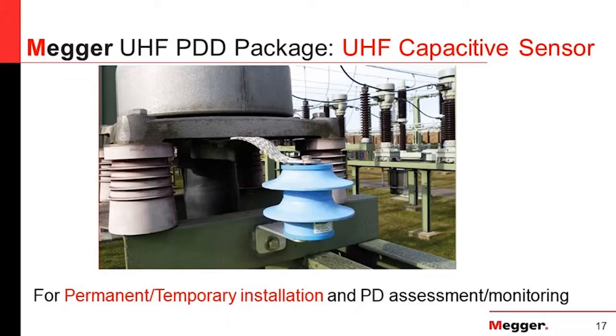Then we have a UHF capacitive sensor, which should be put in between the earth of the instrument and the ground. It is very, very effective. It can be installed permanently for online monitoring purposes. So you can install tens or hundreds of these on any equipment you want to monitor.